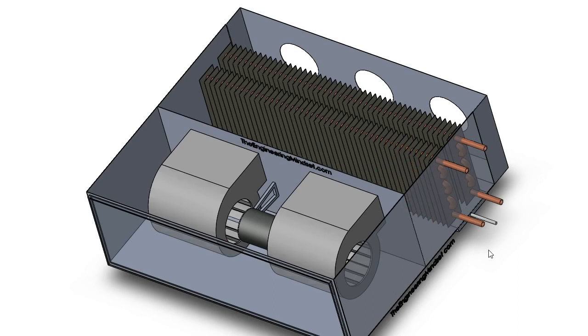Now the heating and cooling coils, they just heat the air up or cool it down depending on the requirements for the local environment. You may have just one coil in there, it could just be a cooling coil or it could just be a heating coil, or you may have both of them like this where the air can be heated or cooled. So these coils are fed, say this one's the heating coil here, so this is fed hot water from the boiler, and this coil here is the cooling one, so this is fed cold water from the chiller.